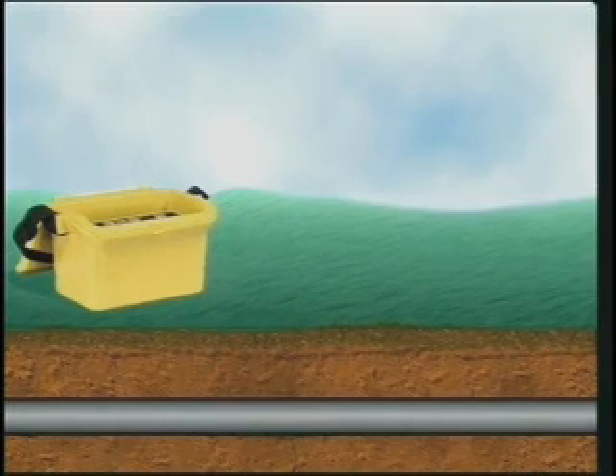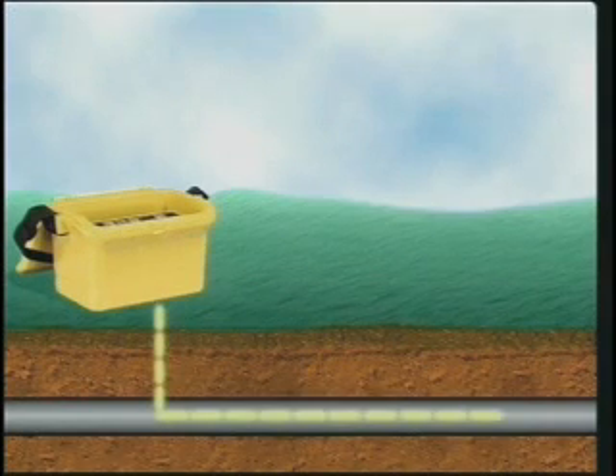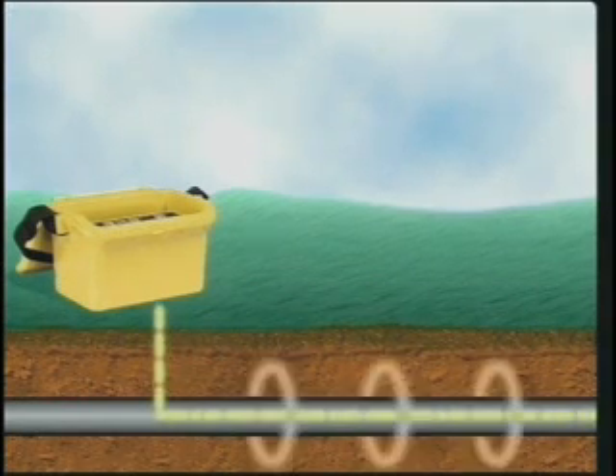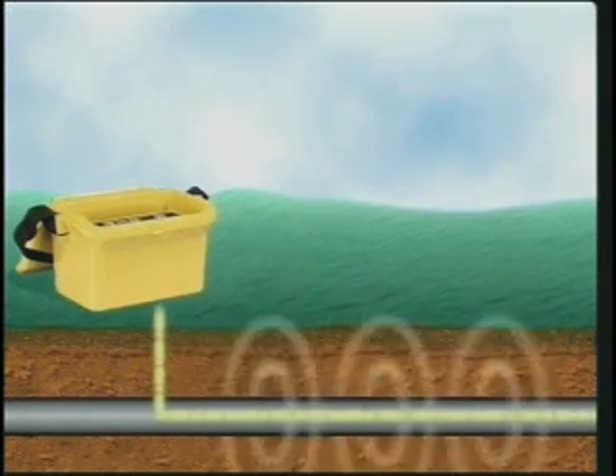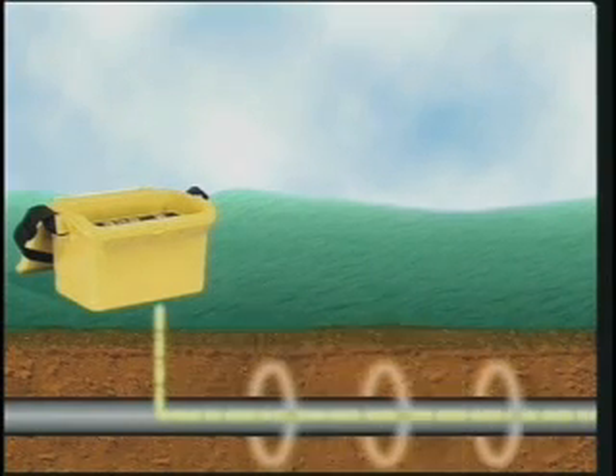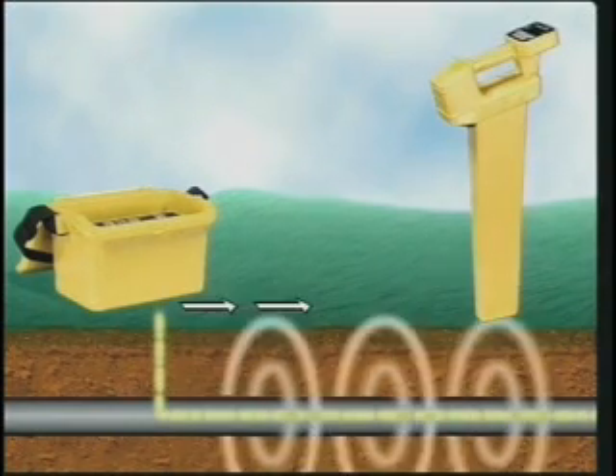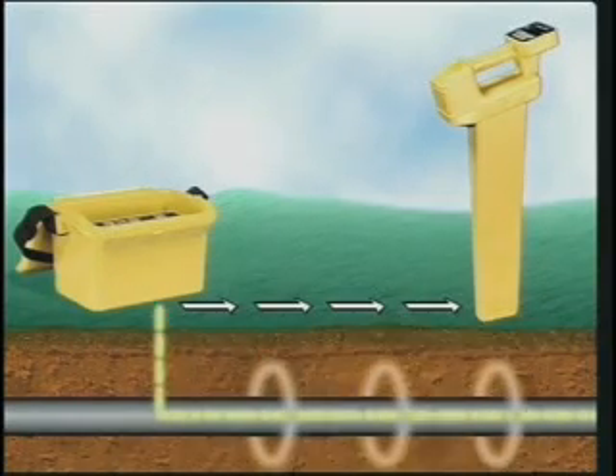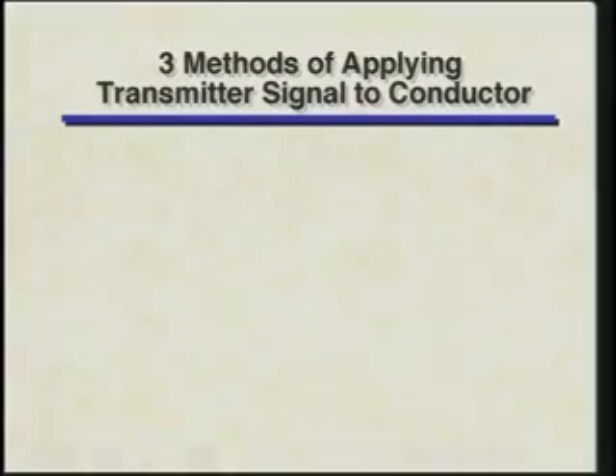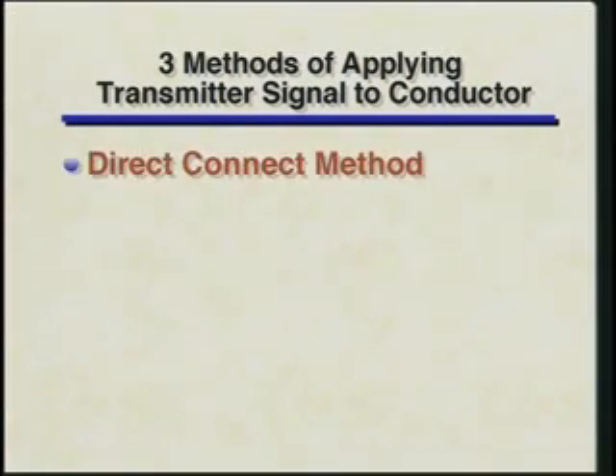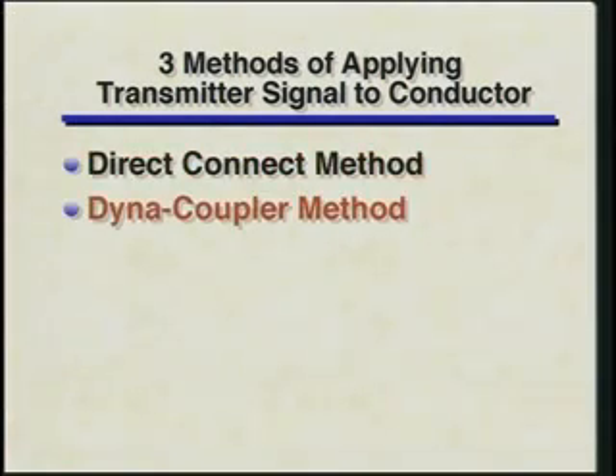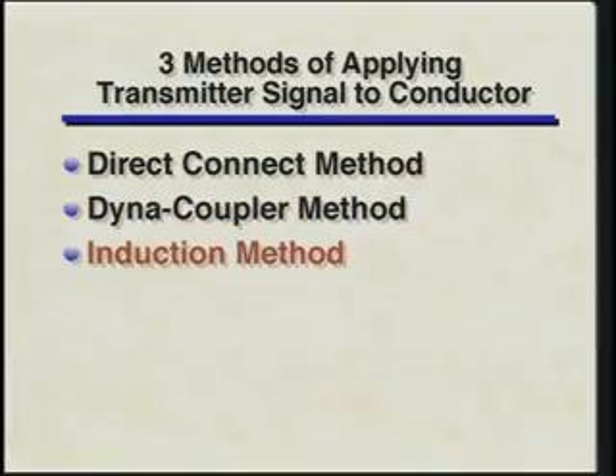When you're tracing a buried conductor, the transmitter sends a current through the conductor. The current causes an electromagnetic field or signal around the conductor. The receiver detects the field, allowing you to trace the path on the surface. There are 3 methods of applying transmitter signal to a conductor: the direct connect method, the dynacoupler method, and the induction method.